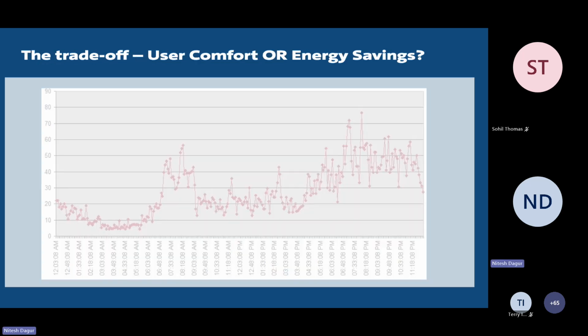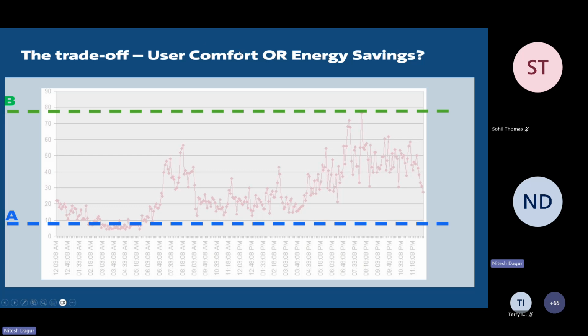So looking at it, there are several ways that we can size the pump, and we can understand how we can meet the demand in the building actually. So this is the bare minimum that the building needs to operate at any given point in time. And this is the maximum need of the building that can happen during a day or during any given period of time, actually. So which one would we be more inclined to size the pumps for?